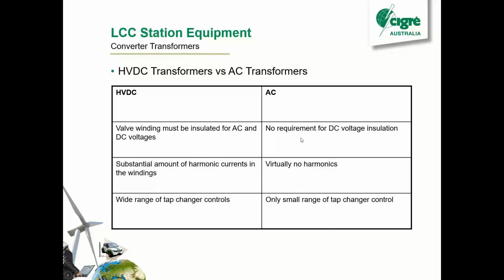It is worth noting that for some VSC schemes, if you use the symmetrical monopole arrangement, you can just use a normal AC transformer. And yeah, Les talks about it in his presentation. But that's the one exception. If you've got a symmetrical monopole VSC, you don't need a special HVDC transformer.